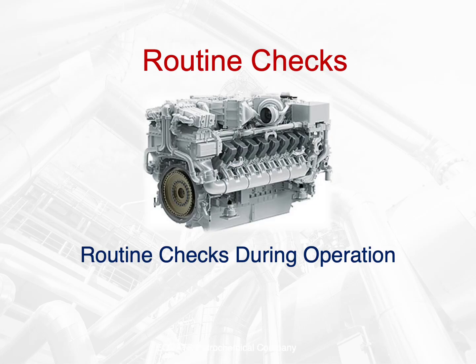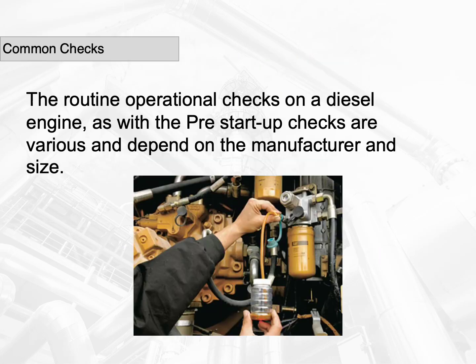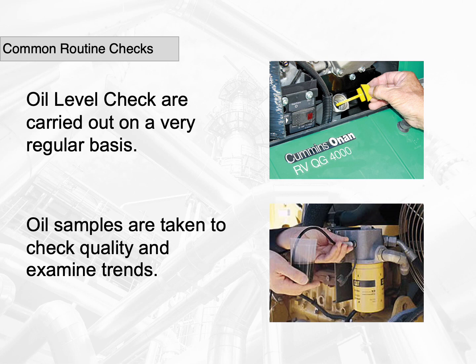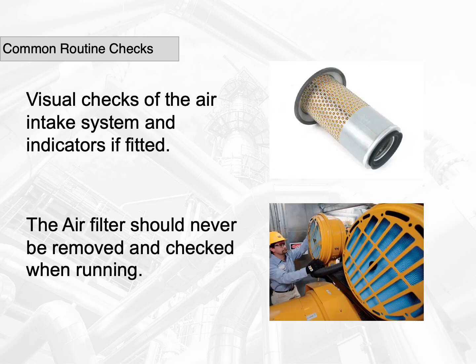Routine checks during operation. Common checks. The routine operational checks on a diesel engine, as with the pre-startup checks, are various and depend on the manufacturer and size. Common routine checks: oil level checks are carried out on a very regular basis. Oil samples are taken to check quality and examine trends. Visual checks of the air intake system and indicators, if fitted. The air filter should never be removed and checked when running.